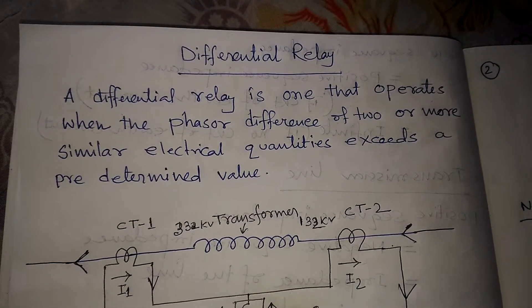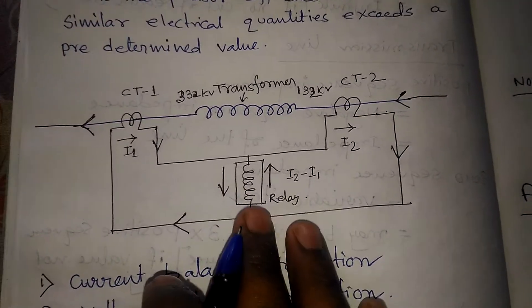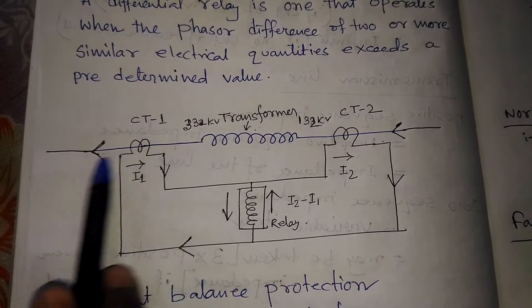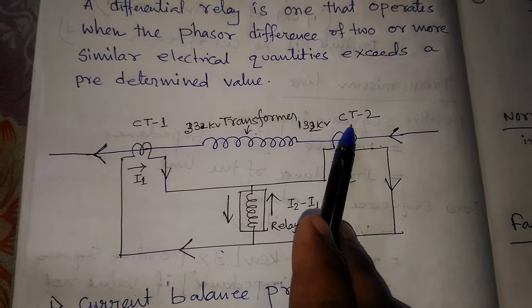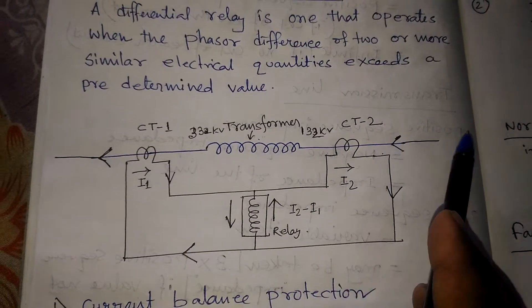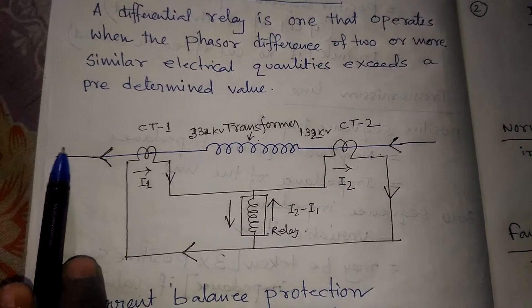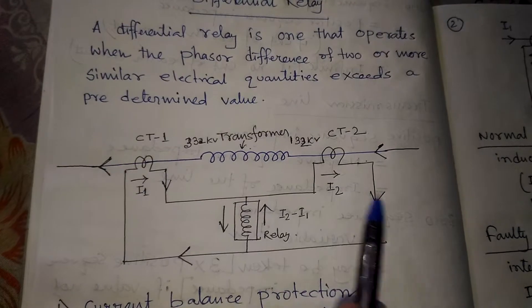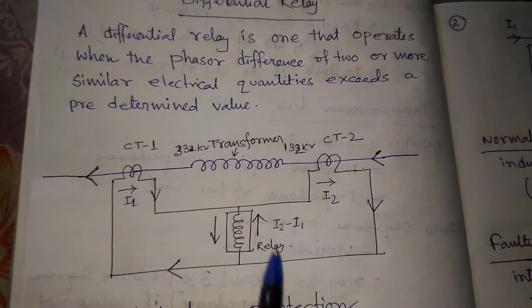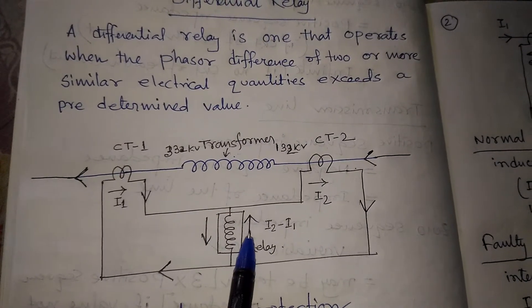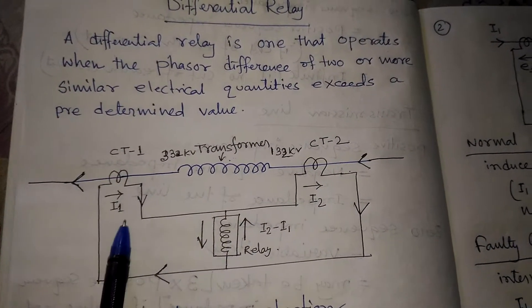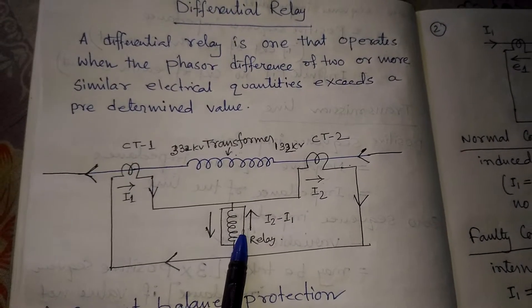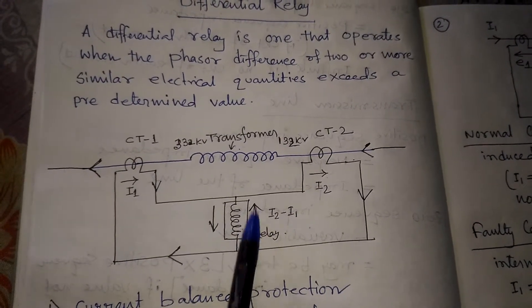Suppose in a circuit, current is flowing in normal condition — I1 current and I2 current are flowing. As far this diagram is concerned, if it is a transformer, this is the primary and this is the secondary CT. The CT current will flow in the opposite direction. So I1 current is flowing in one direction and I2 current in the other direction. The current flowing through the relay coil is I2 minus I1. If I1 and I2 are equal to each other, then zero current is flowing through the operating coil, so the relay will not operate and trip the circuit breaker.